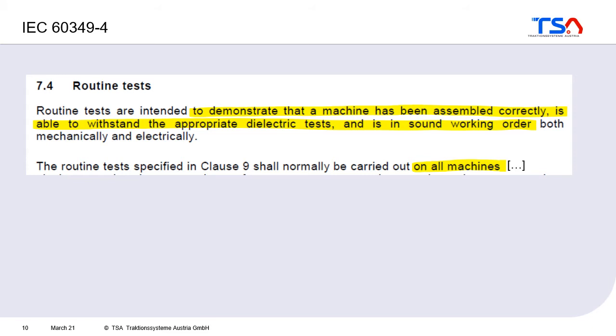Additionally, on every machine manufactured, a routine test is performed. This routine test demonstrates that the machine has been assembled correctly, can withstand dielectric tests — confirming the insulation is okay — and runs smoothly. It is not the full type test program but a reduced test, and it must be done on all machines before delivery.